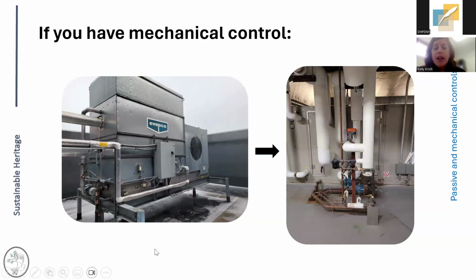Your chilled water is either going to come from some kind of tower within your own facility, or if you're on a municipal or campus supply, you might have it piped in from somewhere else. To the right there, you can see an image of some of the chilled water going in. Usually it's fairly easy to tell where the cooling coil is in a mechanical system because you'll see all these pipes, as well as some pipes coming out. You may even see in the summer what looks like water coming out of it. That's the condensate, what's condensed out of the air coming out of the system and being directed towards a drain.